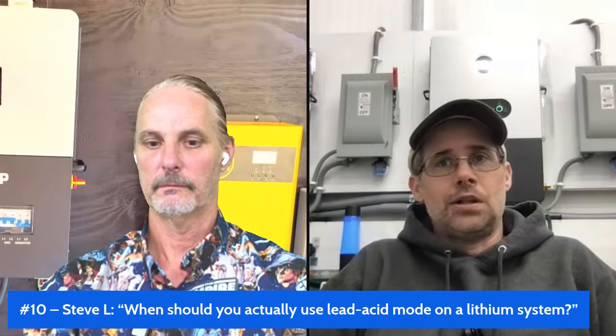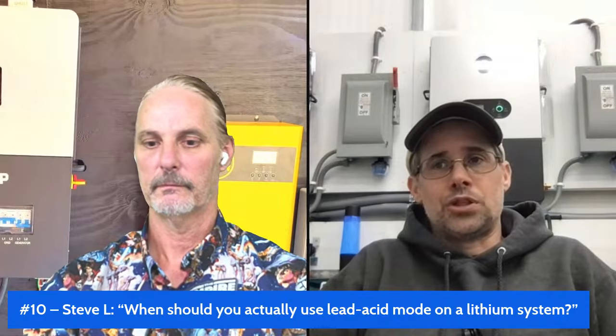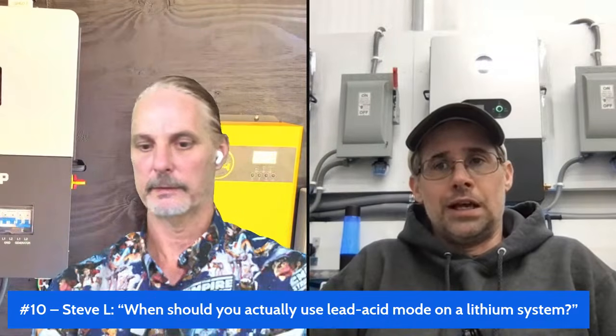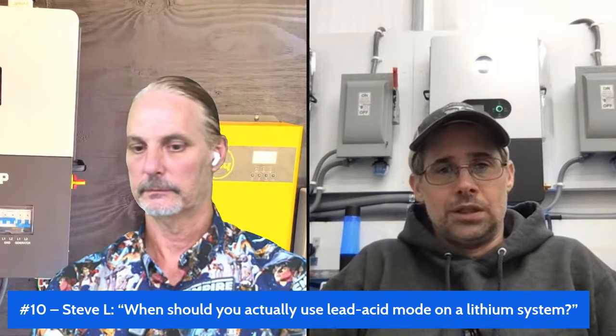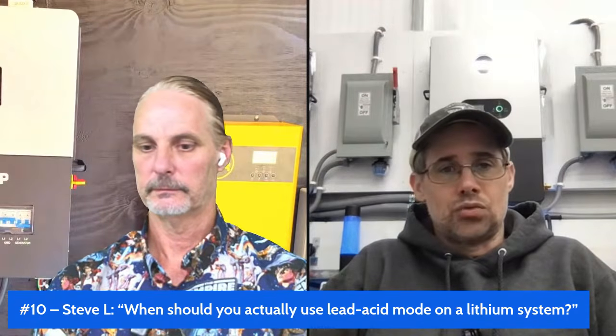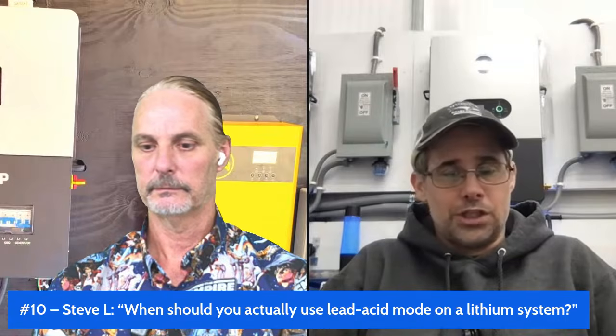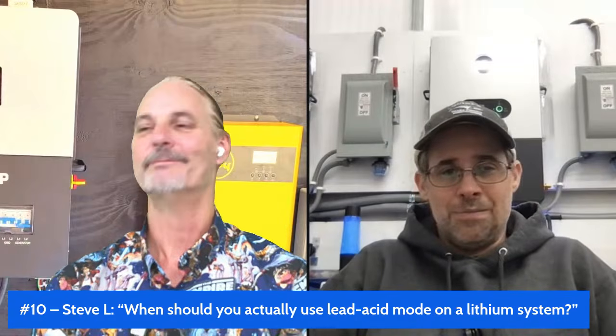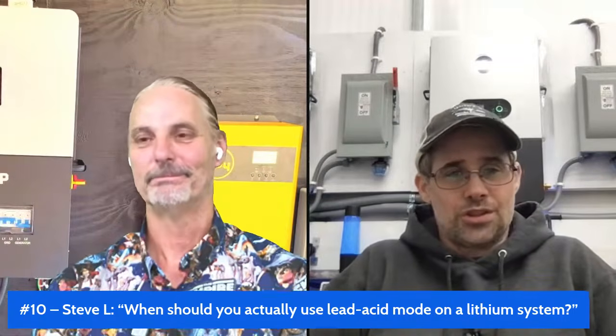I've seen a lot of people connecting up their system saying, I can't get it to work, I can't get the inverter to turn on because it's not communicating. My response is, why are you even doing it that way? Just switch to voltage and it will put it in lead acid mode, and it just works.